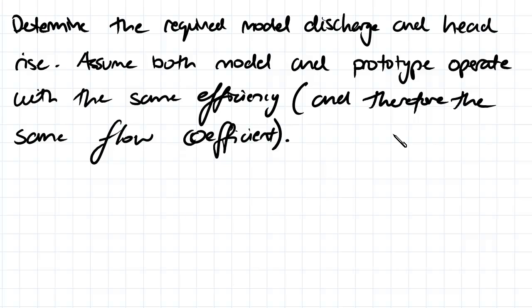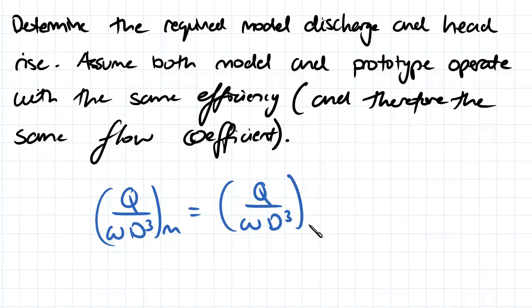First thing we need to do is work out what that model discharge needs to be. To do that, we're going to use the fact that they have the same flow coefficient. So that means that our flow rate divided by our angular velocity divided by our diameter cubed for the model has to be equal to our flow rate divided by our angular velocity divided by our diameter cubed for the prototype.